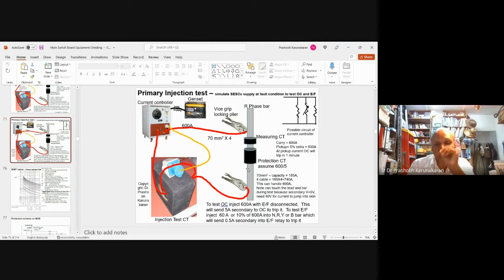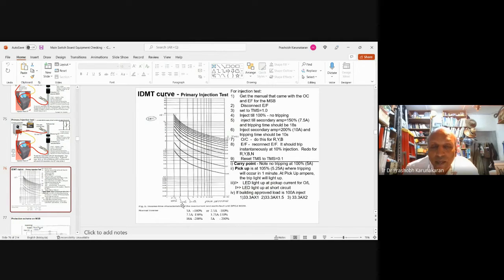According to this graph, let's see — at 150%, looking at this graph, it should trip here, at 7.5 amps. Then at 200%, it must trip at 10 amps.